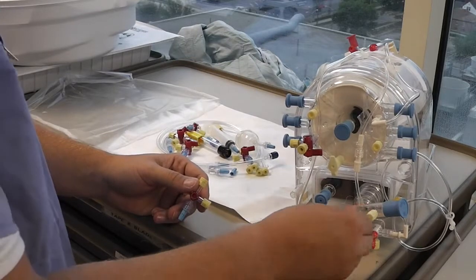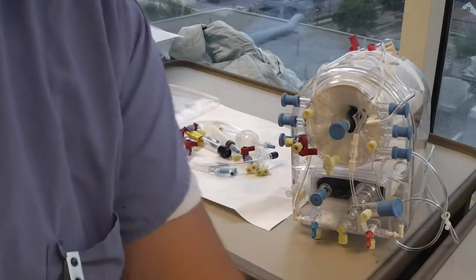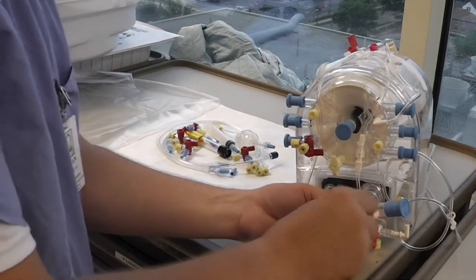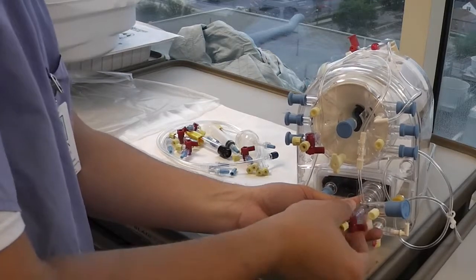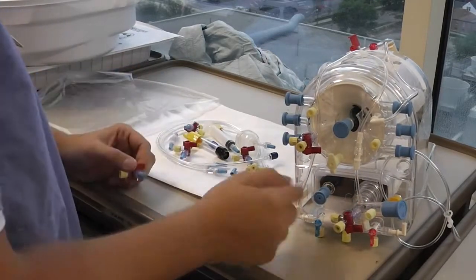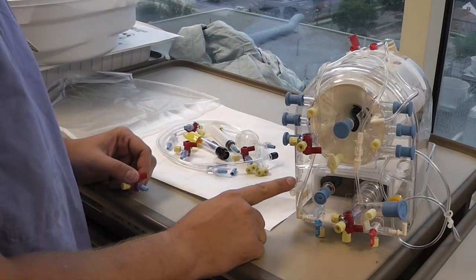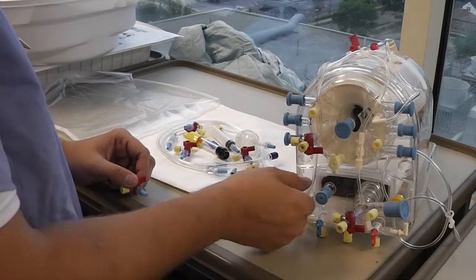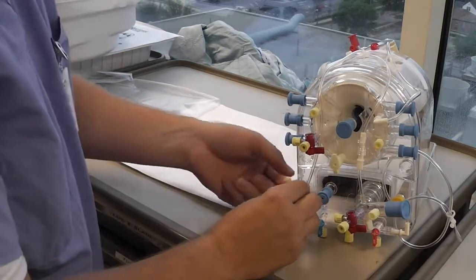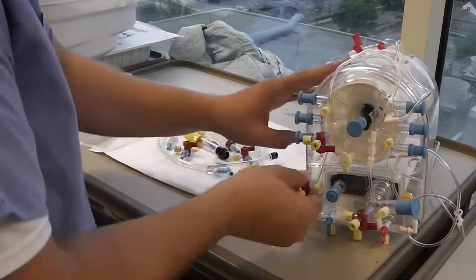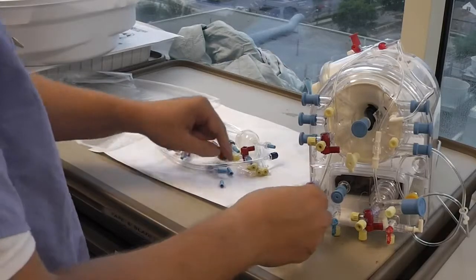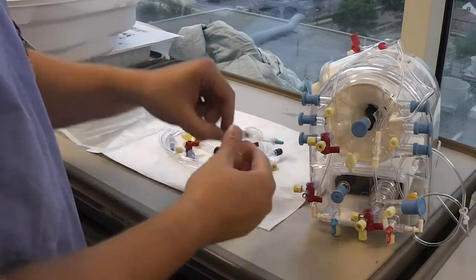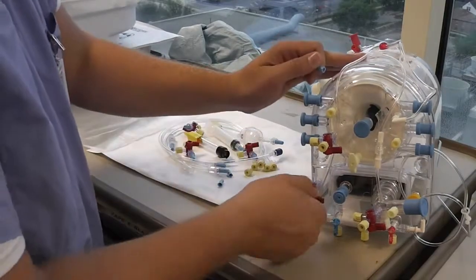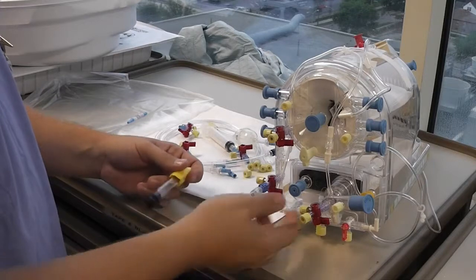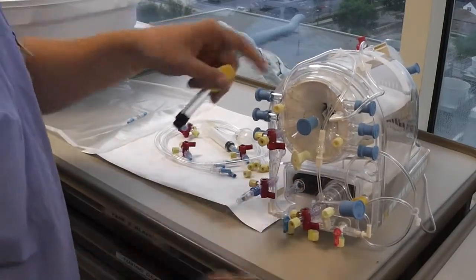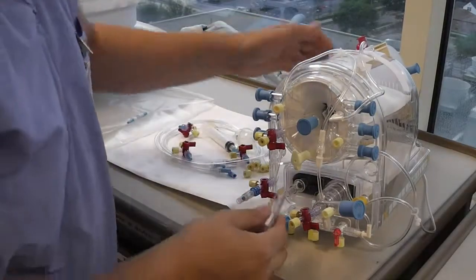We're going to put one here on the venous return line. This isn't really used much anymore, but it's occasionally used when we have drugs that we're putting in from an infusion pump or something like that. Down here we have the positive pressure relief valve. This isn't always on here, sometimes there's just a cap, but we're going to remove that. Put a stopcock there. And if it came with one, you can either put that factory one back on, or in the pack here there's this other one that you can put on. Either one will work. Alright, now we're going to put the negative pressure relief valve on. It attaches to this cap, pull that off. The yellow cap comes off, and then make that connection.